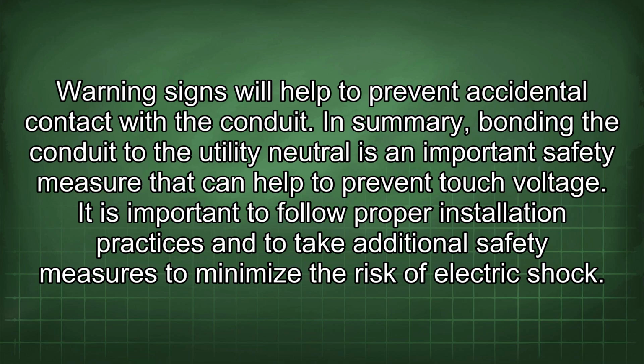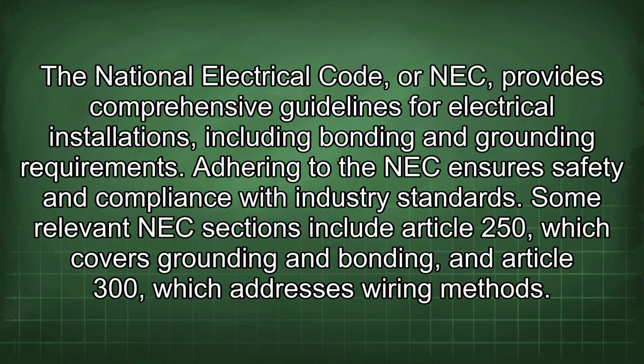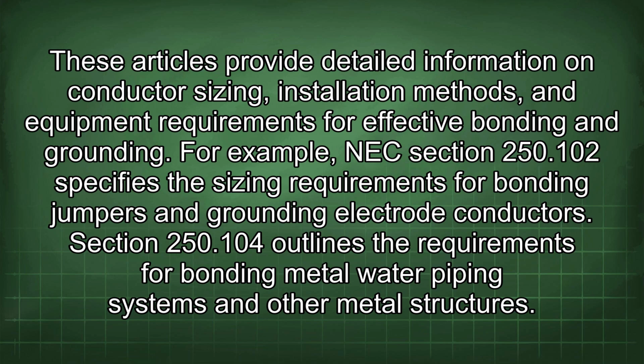In summary, bonding the conduit to the utility neutral is an important safety measure that can help to prevent touch voltage. It is important to follow proper installation practices and to take additional safety measures to minimize the risk of electric shock. The National Electrical Code, or NEC, provides comprehensive guidelines for electrical installations, including bonding and grounding requirements. Adhering to the NEC ensures safety and compliance with industry standards. Some relevant NEC sections include Article 250, which covers grounding and bonding, and Article 300, which addresses wiring methods. These articles provide detailed information on conductor sizing, installation methods, and equipment requirements for effective bonding and grounding.